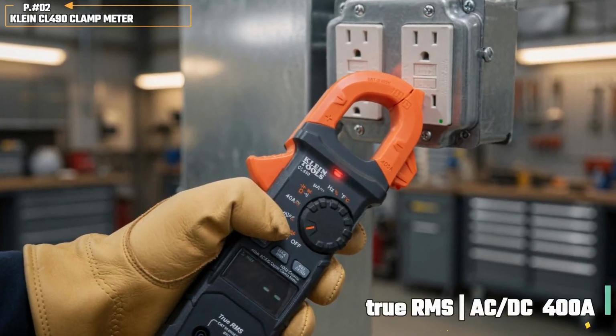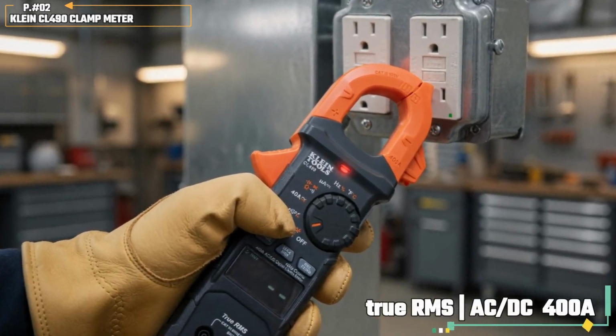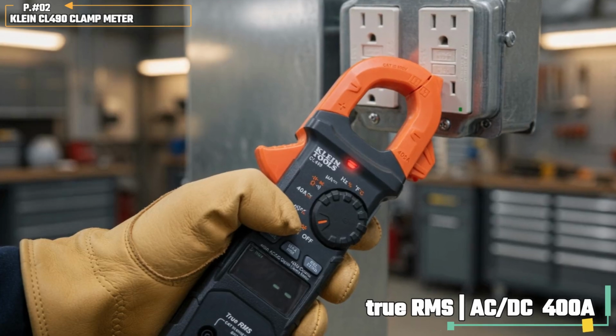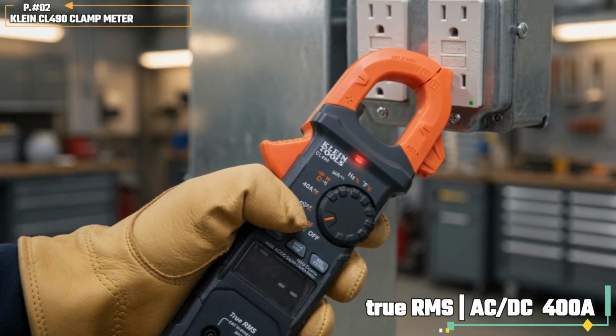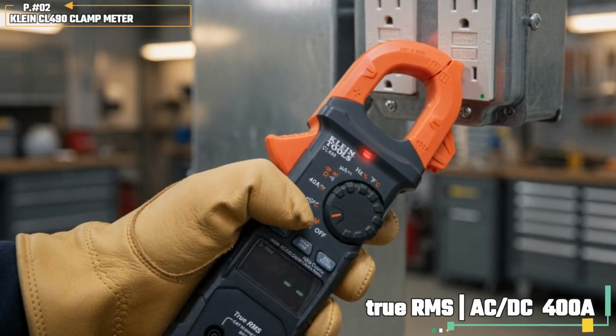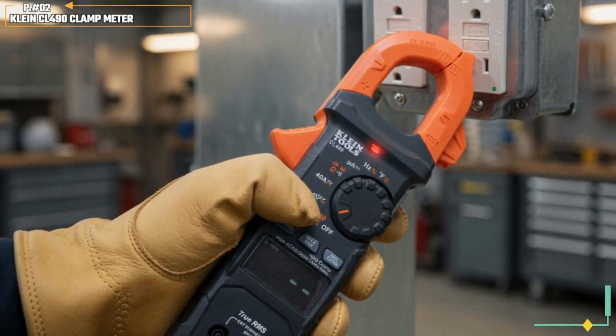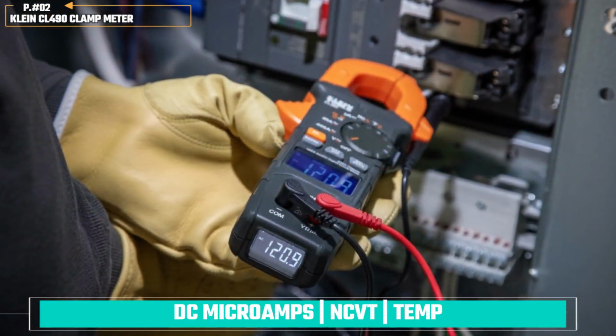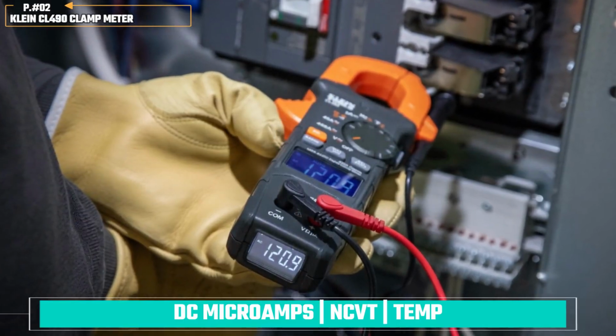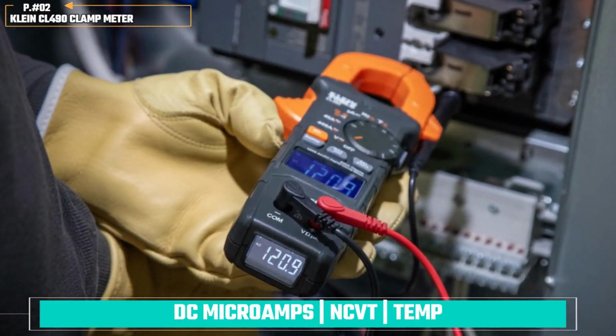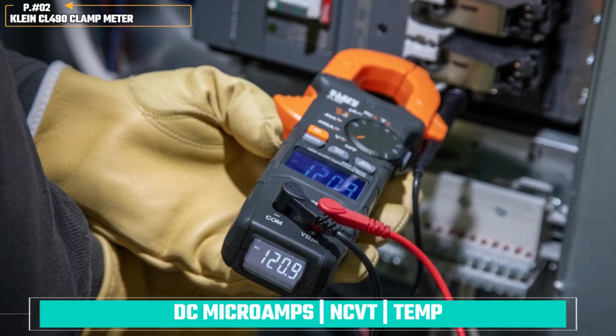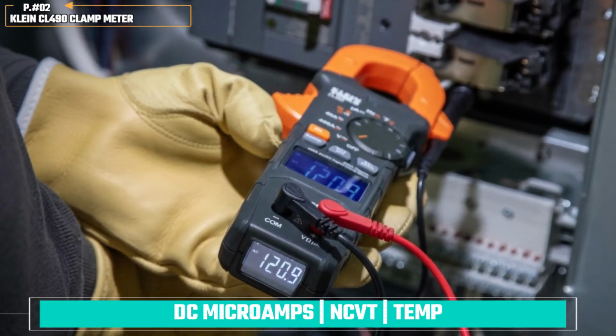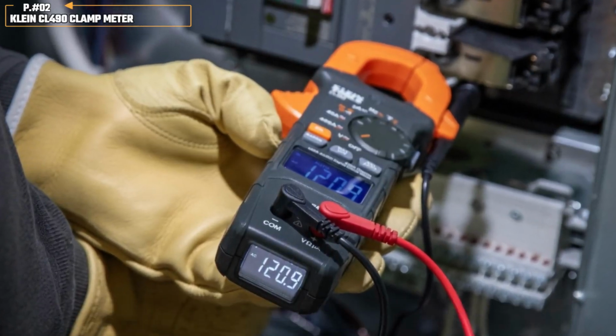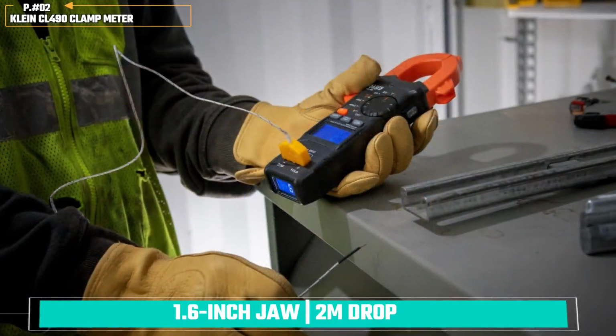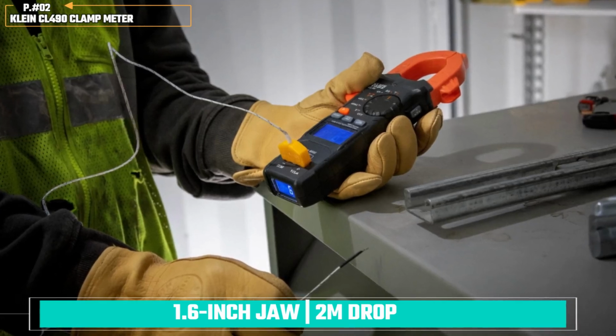The True RMS system measures AC and DC current up to 400 amps and AC or DC voltage up to 600 volts. It also measures DC microamps, making it useful for checking furnace flame sensor circuits and other low-current controls. Through the test leads, it measures resistance, continuity, frequency, duty cycle, capacitance, and diodes. The included thermocouple adds temperature testing, while NCVT provides escalating sound and visual alerts as the meter approaches an energized AC source. The 1.6-inch jaw provides room for larger individual conductors.